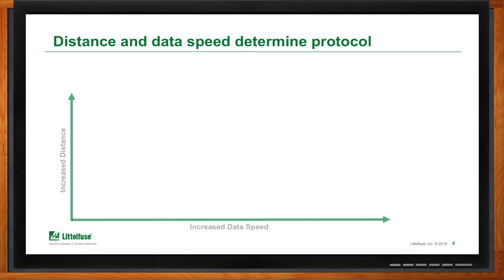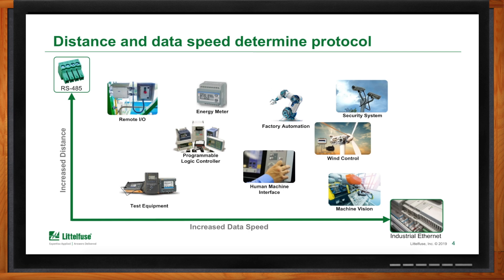So Craig, where would you tend to use RS-485 versus Ethernet? Typically you'd want to use Ethernet when you have a lot of data transmission — for example, security cameras or machine vision systems. You'd want to use RS-485 for longer transmission links, such as remote I/O or applications out in the field like energy metering.